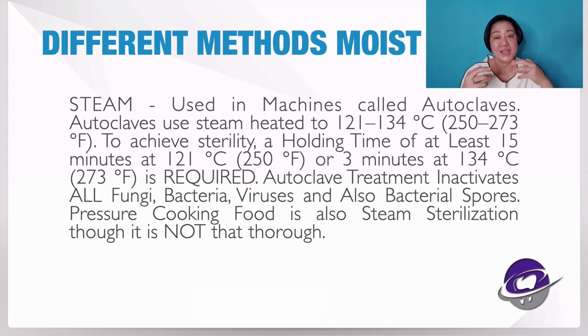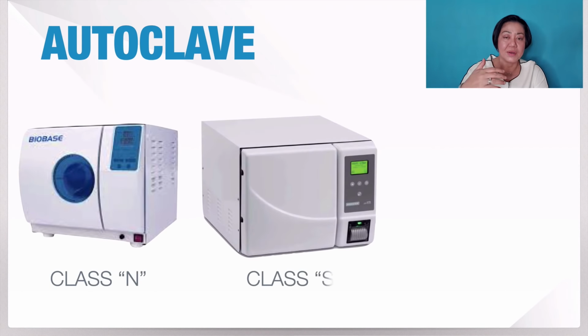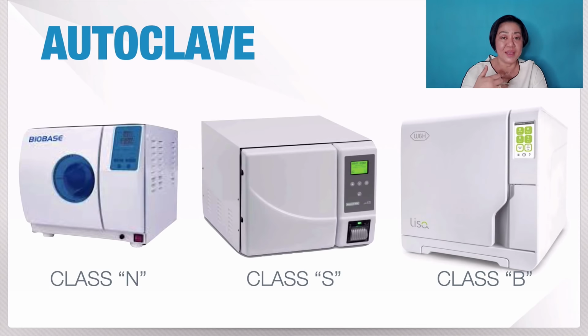And that is the reason why bunching up all these instruments in one pouch so that we can save the pouch will not work, or putting so many pouches in one cycle of autoclaving will also not work. So again, there are different types of instruments that can be sterilized on a specific autoclave. The autoclave, although it is very dependable and evidence-based to sterilize all our instruments, is still not 100%. Why? Because of human error or not following instructions, and sometimes the autoclave has its own maintenance. That's why there's data that it releases that shows you whether the autoclave is working properly.